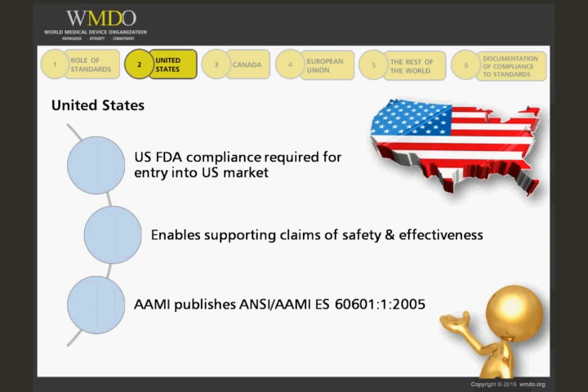which is the third edition standard, but it also includes the U.S. deviations. U.S. deviations are differences in the standards specific to the United States, and they're to meet the requirements of the National Electric Code and some other requirements. AAMI-ES60601-1 has been updated to include the text of Amendment 1 of 2012.